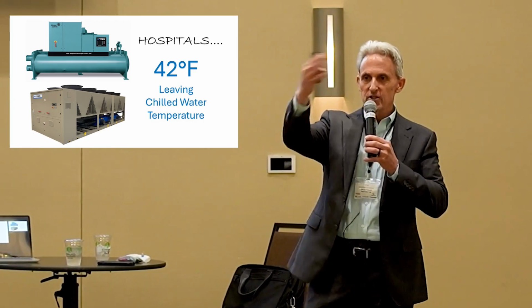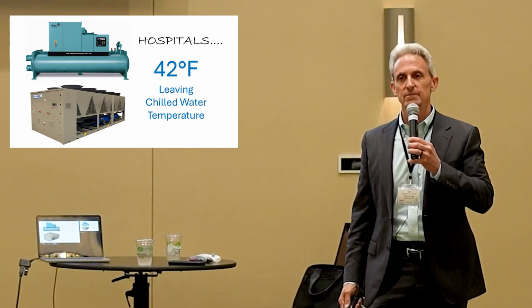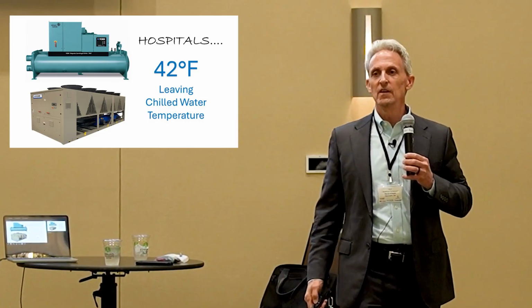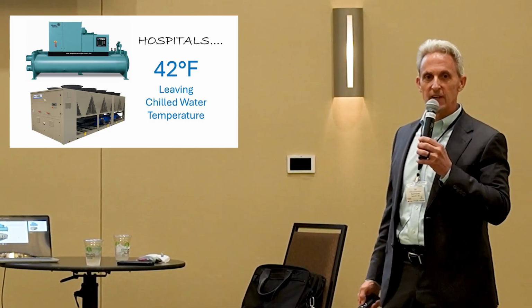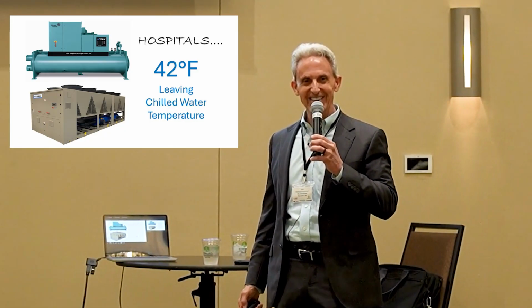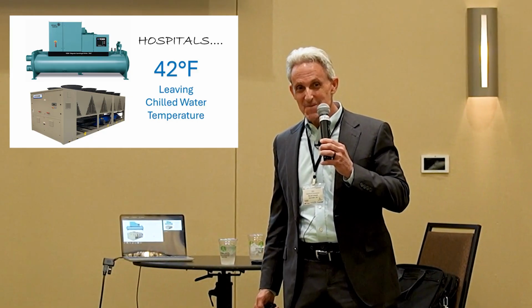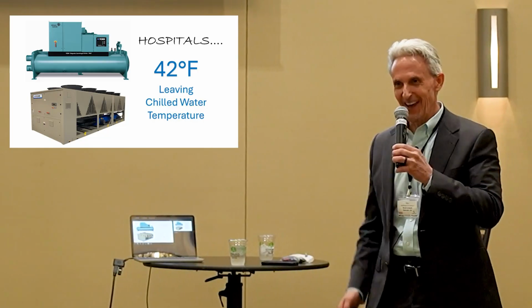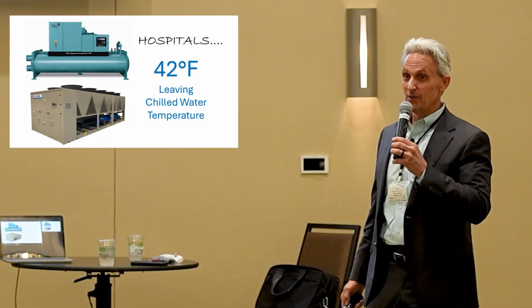So, to my hospital facilities managers in the world, let's put some brass tacks to this now, right? What chilled water temperature are you running in your hospital? 40, 41? Anybody else? Come on, I see you smiling. You got a number? It's okay. Oh, you're with him? Okay. 40, 41's kind of low for a hospital.